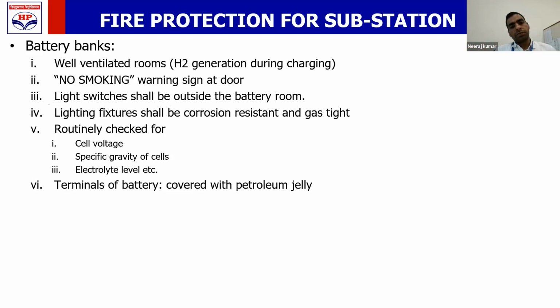Light switches should be provided outside the battery room. Why? Because there will be hydrogen generation during charging, and this hydrogen may be a source of fuel for ignition. Light switches are known to generate spark at every switching. So instead of putting flame-proof light switches, it is better to put light switches outside the battery room.